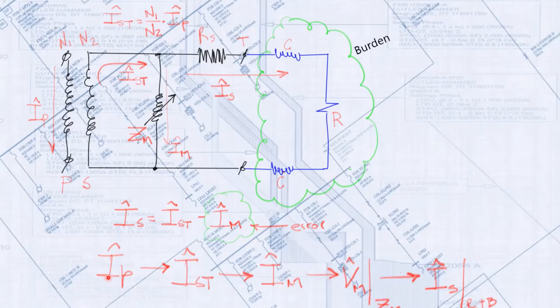The primary current IP drives the ideal total secondary current IST. The total secondary current IST drives a magnetizing current IM which causes the magnetizing voltage VM across a saturation characteristic. It is then this magnetizing voltage VM what drives the relay current IS through the burden and secondary winding. And by the way, I forgot to mention the CT secondary winding impedance RS, right here.